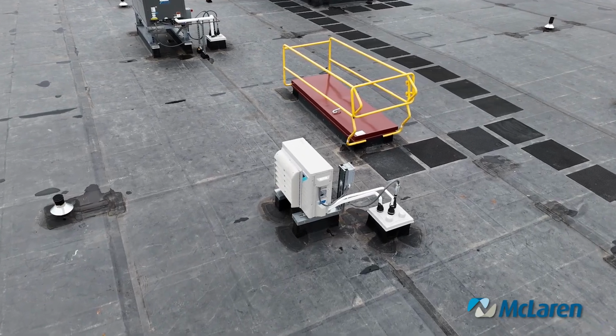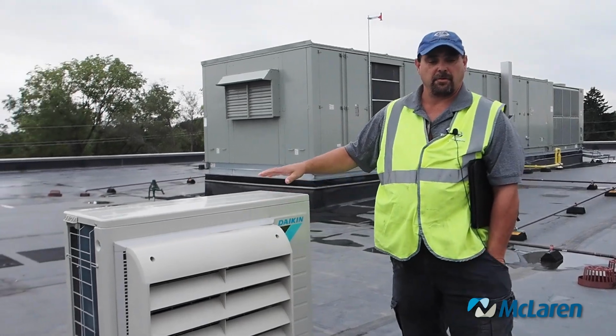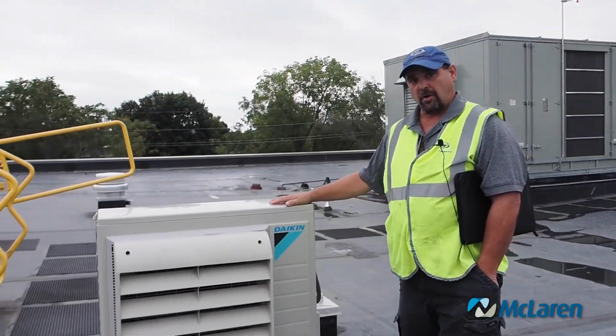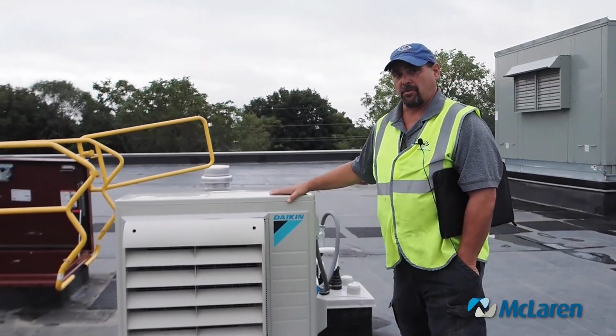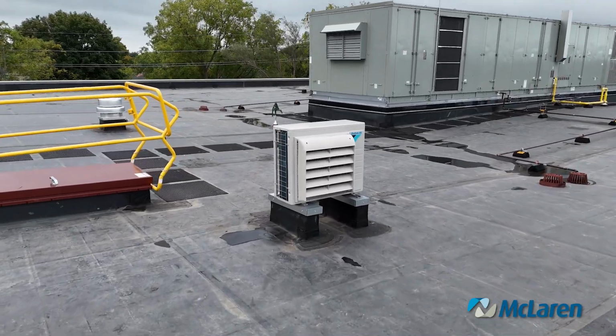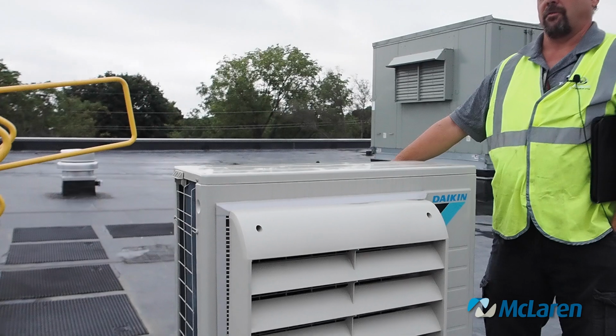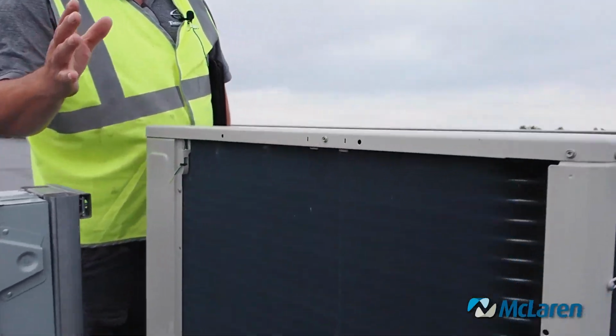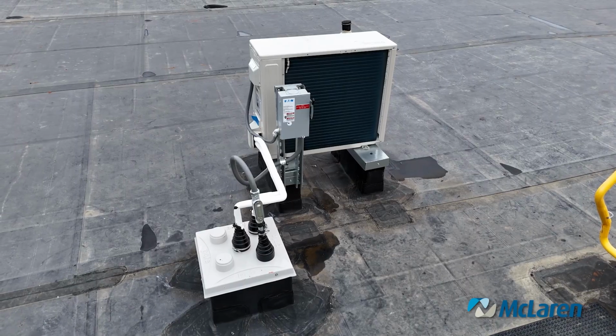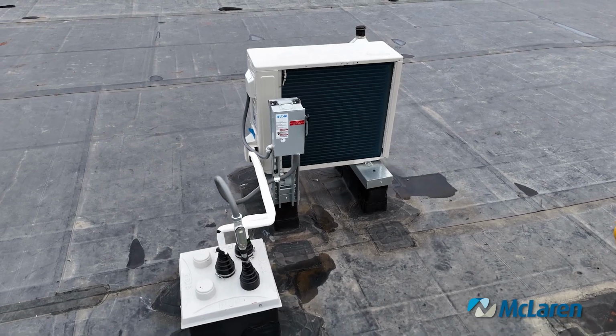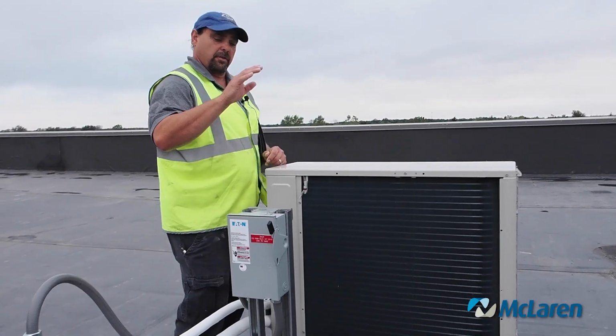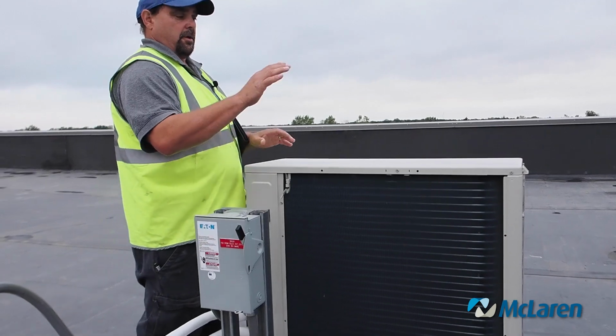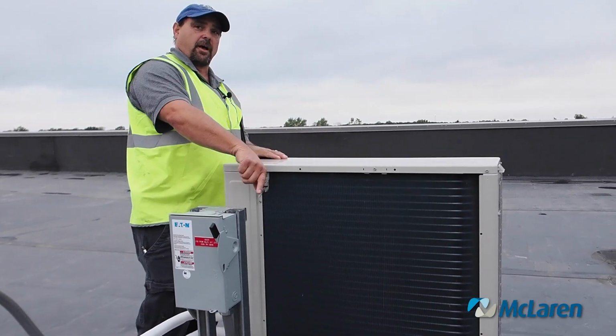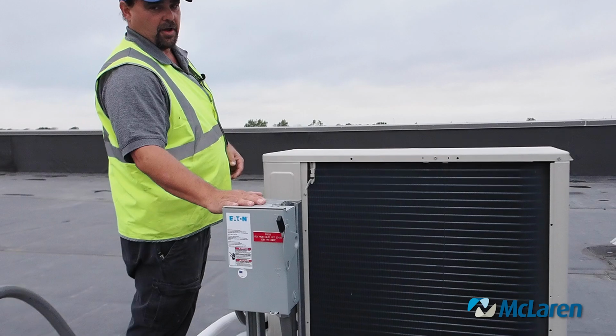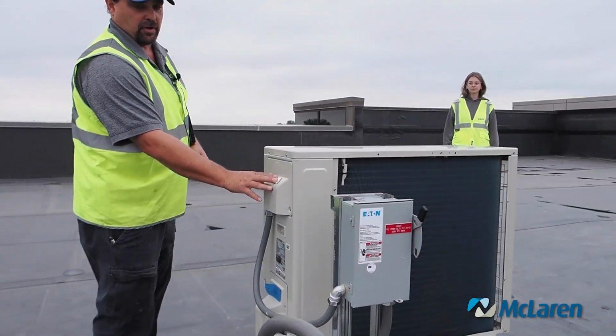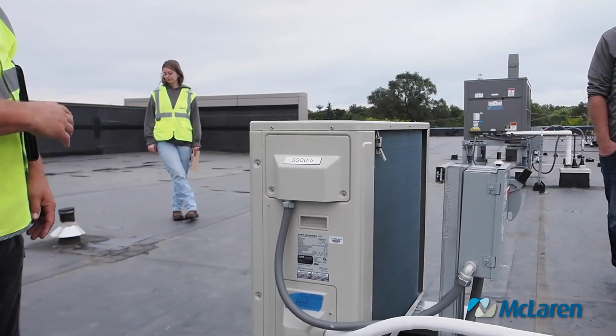This is a condensing section of that evaporator mini split system that we just talked about. On this unit here, there is very little maintenance. The only thing you really have to do is, if you look on the back side, over here is a condenser coil. Keep this coil clean. No pressure washer, no chemicals, just a nice rinsing. And to properly do it, you lock out, tag out, kill power, take the top off, and go from the inside out. Also at the same time, after you lock out and tag out, take the cover off here and check your electrical connections. Make sure they're nice and tight. Do that at least once a year.